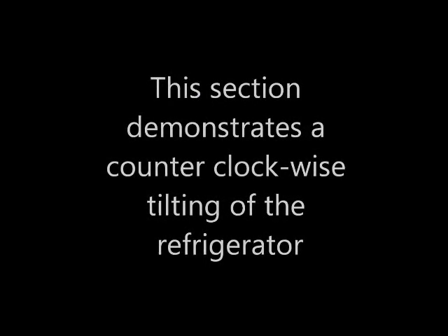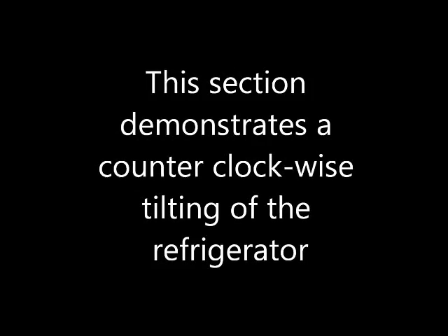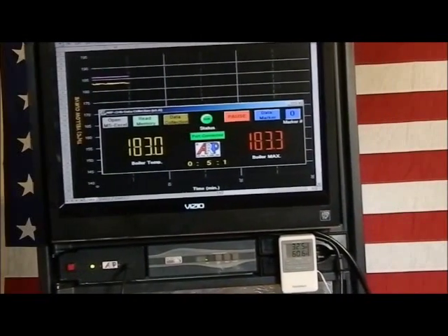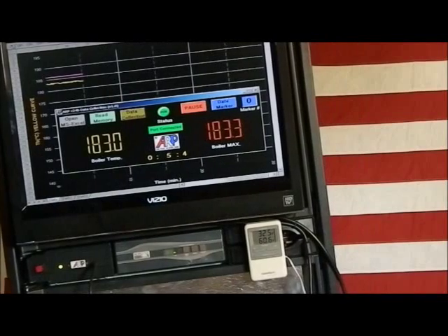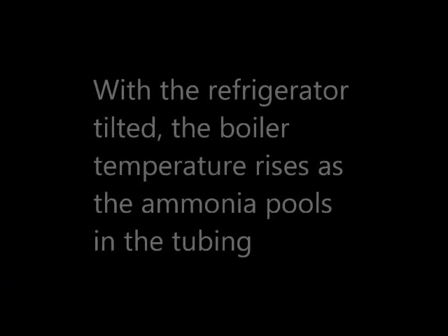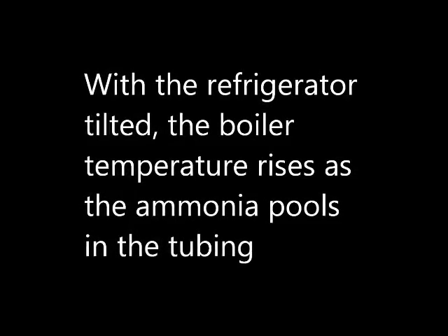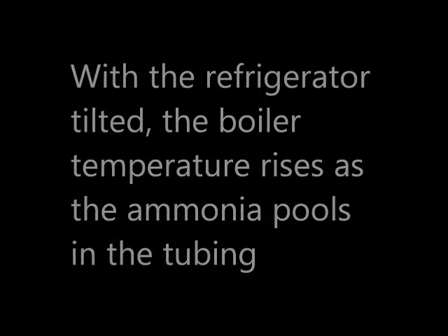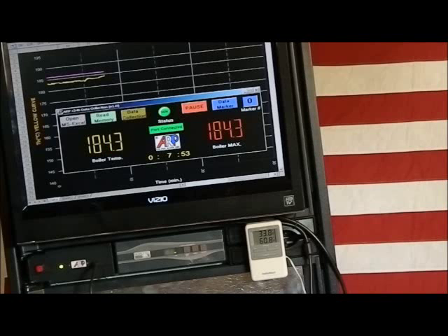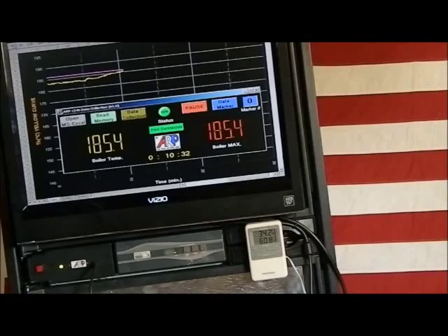This section demonstrates a counterclockwise tilting of the refrigerator using time lapse. The ARP control will protect the refrigerator at any angle of tilt that will cause damage. With the refrigerator tilted, the boiler temperature rises as the ammonia pools in the tubing. At this particular angle and an accelerated playback rate, one can see that the temperature rapidly rises towards the purple set point curve.